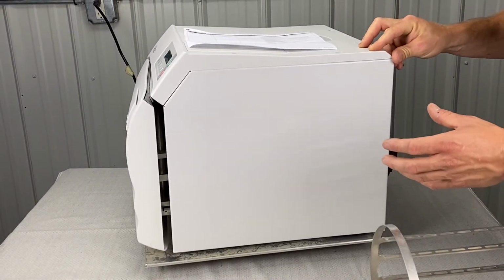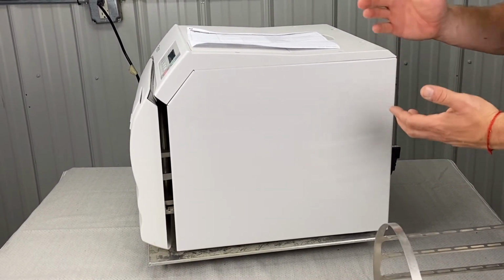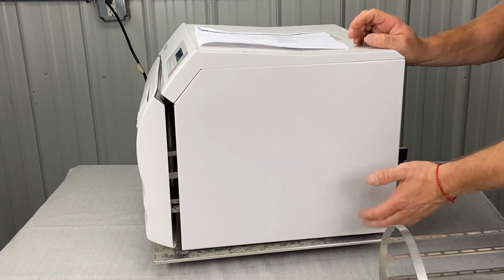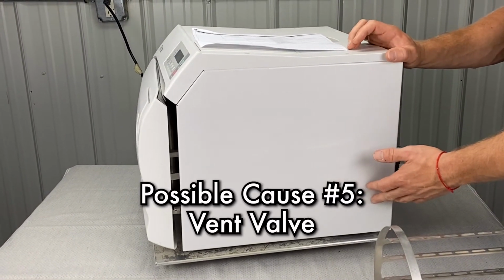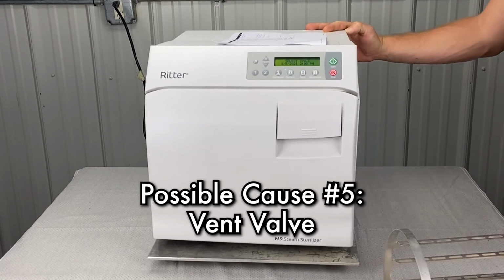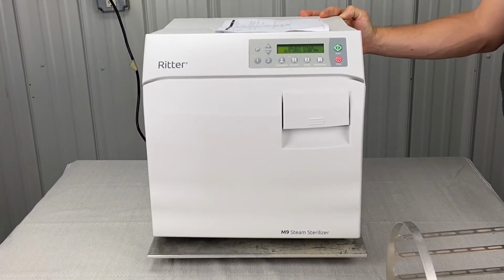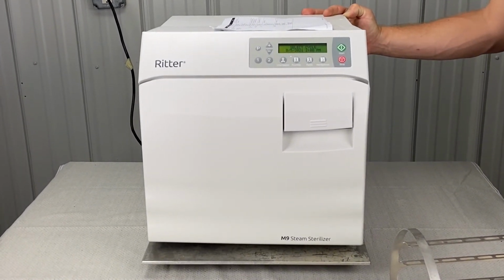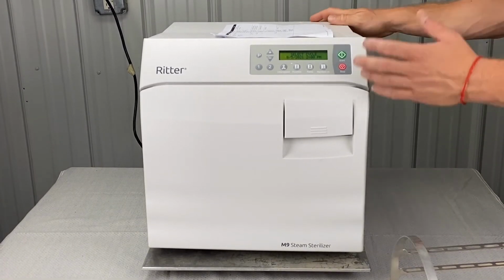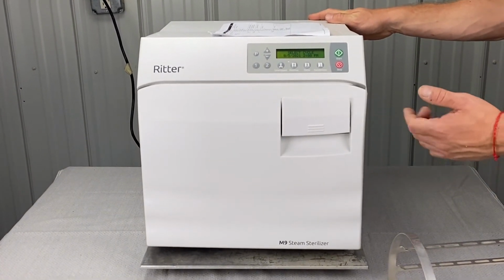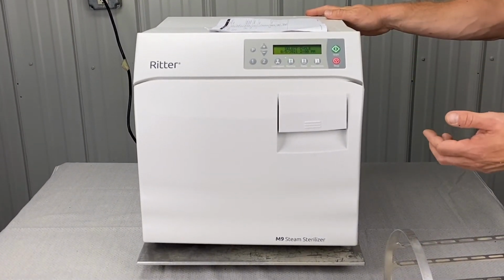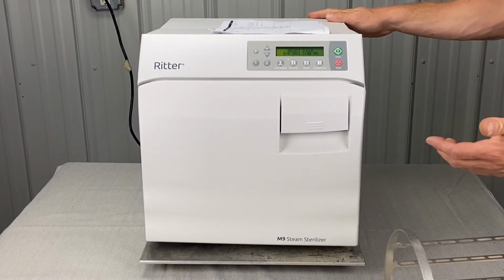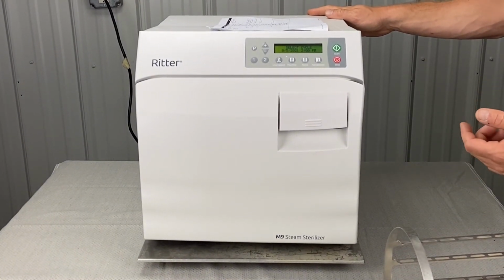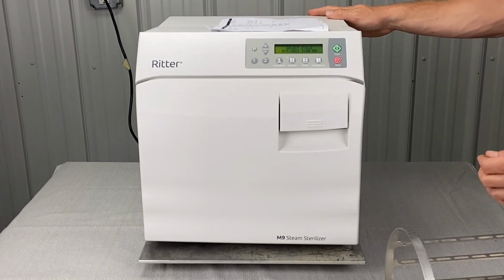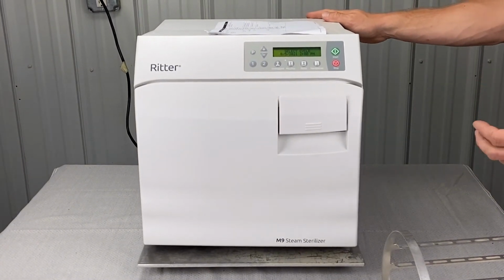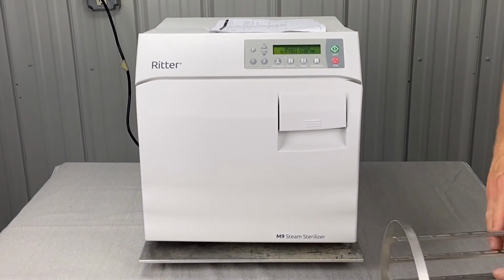Furthermore, the other things are obviously internal. We got a vent valve that could be clogged. The vent valve could be bad. It says with the sterilizer in vent mode, perform the vent valve test. Okay, we'd have to put it into diagnostic mode. You also have to inspect the vent valve, clean valve, stretch spring. So that's another thing that you'll need a special tool for. It's called a spanner nut. You'll probably need an adjustable wrench, and I would recommend calling us, and we can kind of walk you through it a little bit.